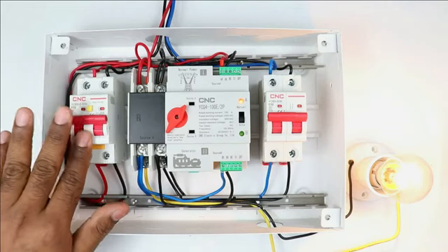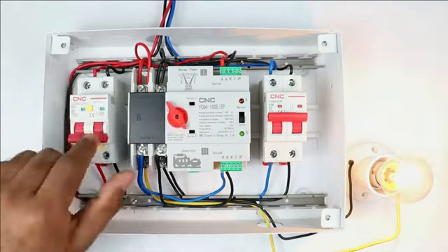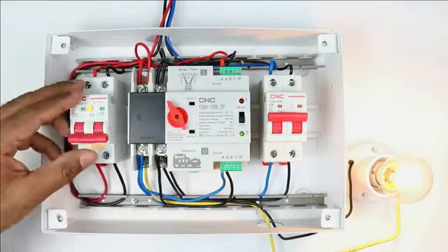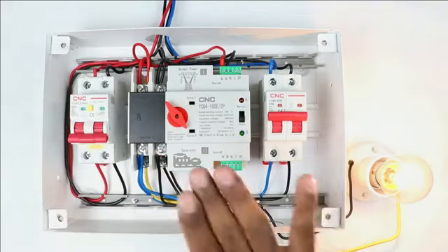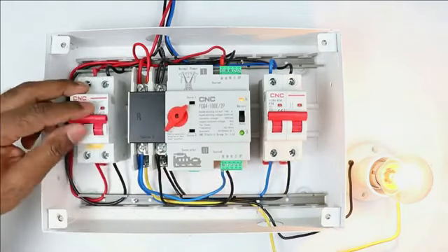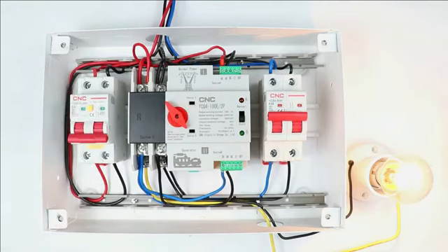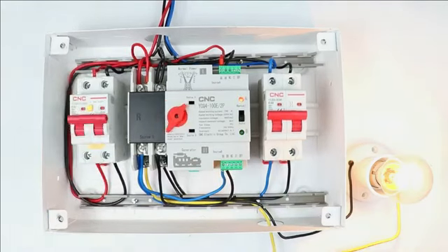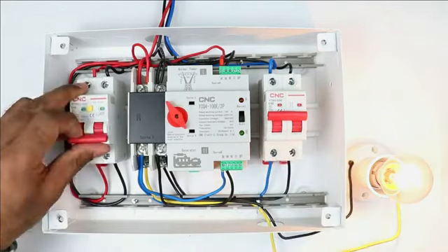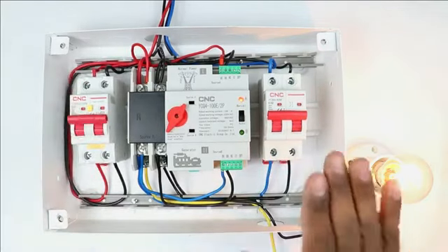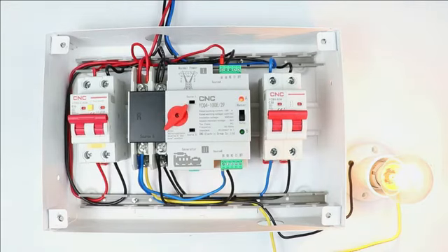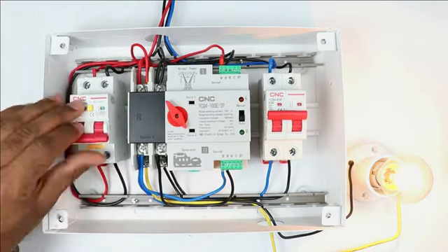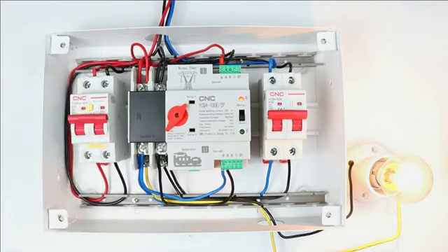What happened is sometimes the main power supply gets tripped and changeover takes place. But when supply comes back and trips again in a few moments, then this ATS performs changeover again and again. What I am saying is, power supply comes back to normal, changeover takes place. When changeover takes place continuously, generator supply is getting on and off again and again, and this should not happen. So today in this video we are going to solve the problem of repeated changeover.